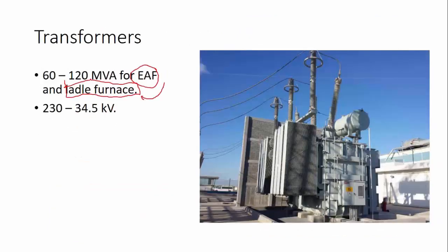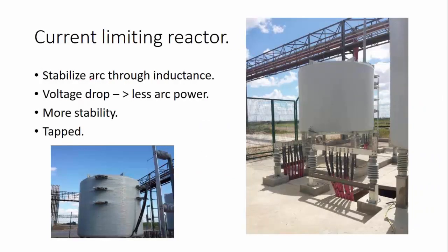So after the main transformer, in some facilities, and this is quite optional, some have it and some don't, you will find a current limiting reactor, which is a huge reactor connected in series between the main transformer and the electric arc furnace. The purpose of this current limiting reactor is to stabilize the arc. It's an inductance, so it doesn't let the current change as abruptly. This reactor will have a voltage drop since it's a series element. Therefore, you'll have less available voltage at the furnace, therefore less power, but a much more stable arc, which is desirable.